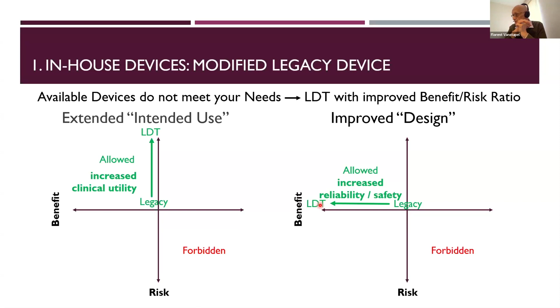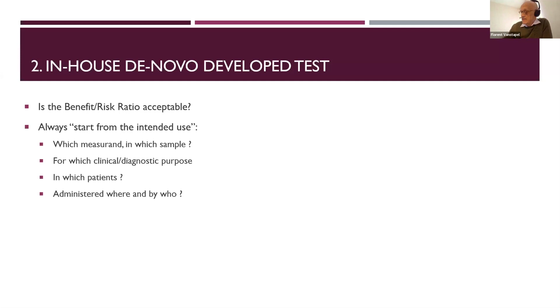For the in-house de novo developed tests, that means that you actually are developing a test that is not available on the market. And the general question of the IVDR is, is the benefit-risk ratio acceptable? And a first way to look at that is we always start from the intended use. We ask a number of questions. Which measurand are we measuring? In which sample? For which clinical diagnostic purpose? Is that the clinical diagnostic purpose that is listed in the IVDR? In which patients do we do this? The test is administered where and by who?